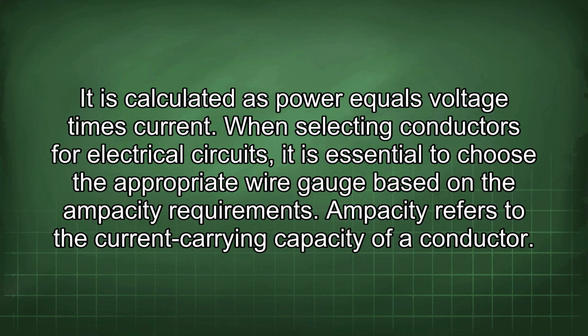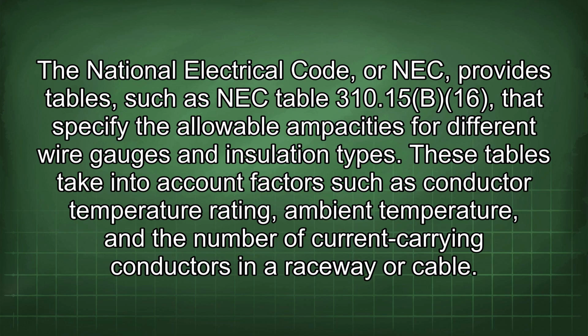When selecting conductors for electrical circuits, it is essential to choose the appropriate wire gauge based on the ampacity requirements. Ampacity refers to the current carrying capacity of a conductor. The National Electrical Code, or NEC, provides tables such as NEC Table 310.15(B)(16) that specify the allowable ampacities for different wire gauges and insulation types.